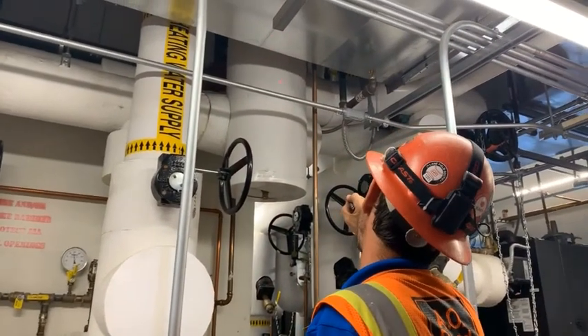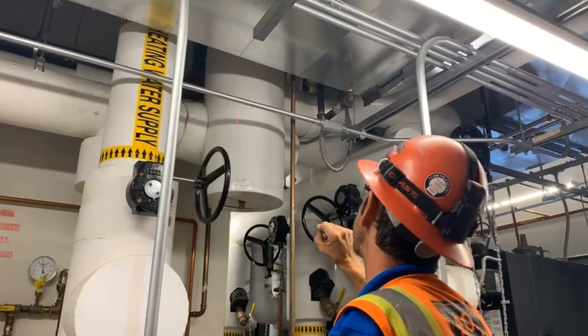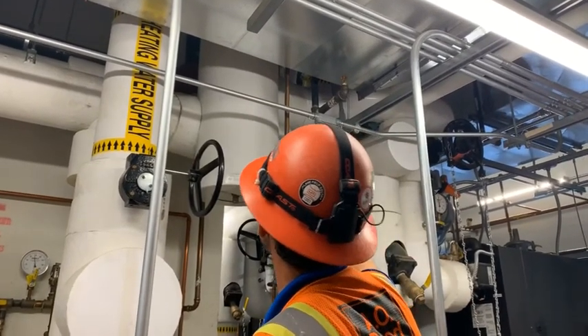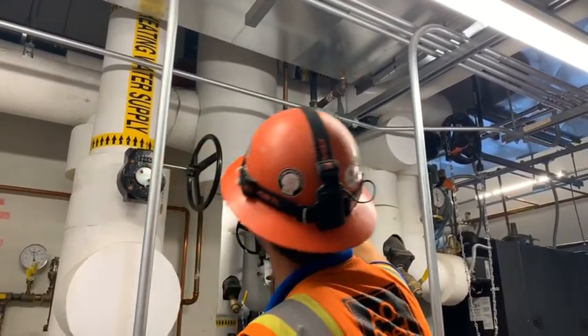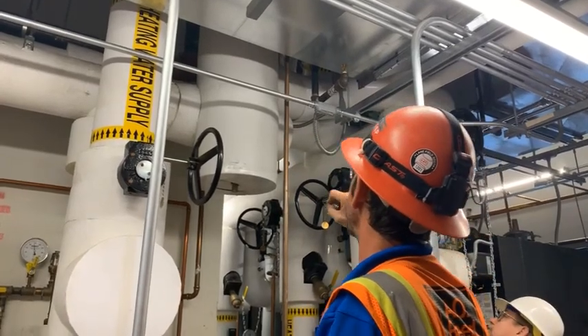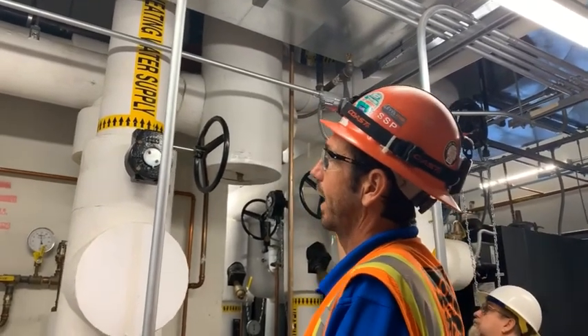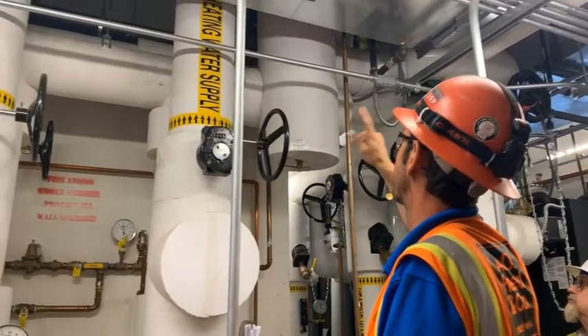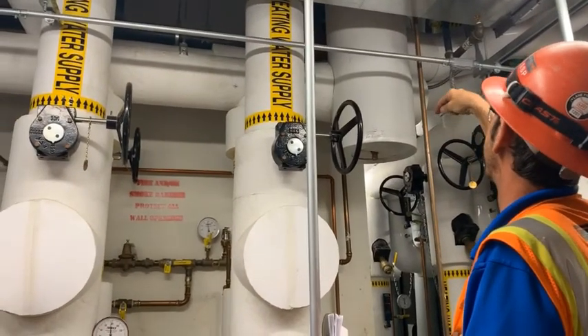This guy right here is your air separator for the heating hot water loop. There's an air vent at the top of that as well. Make sure that valve stays open at all times. That way, as any air makes its way back down from the building, it'll get swirled out of the air separator and vented out the top.